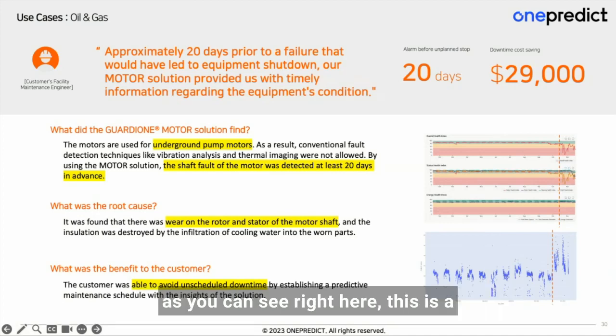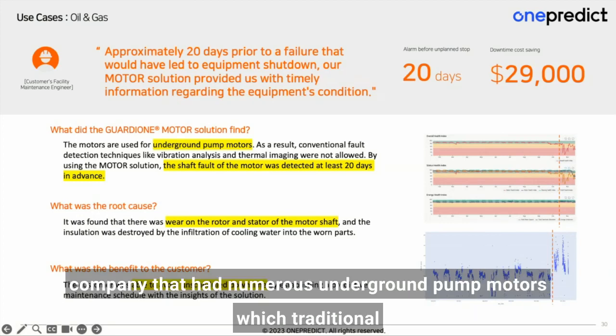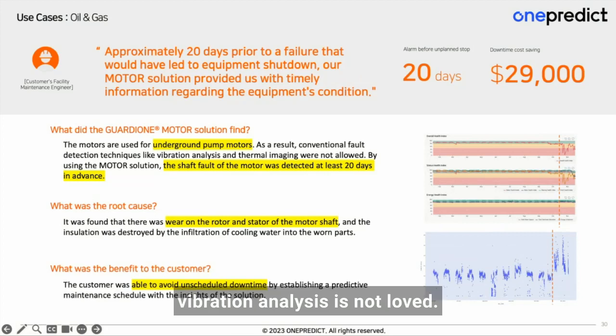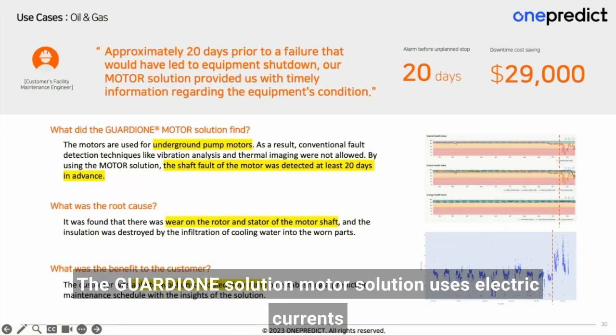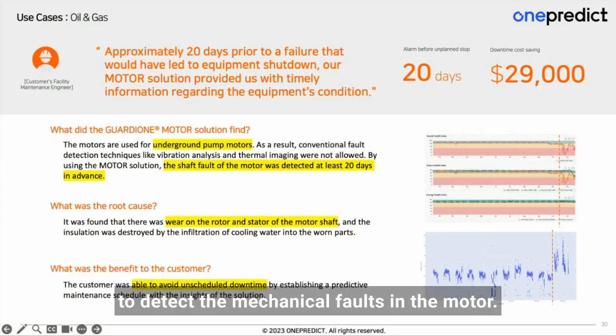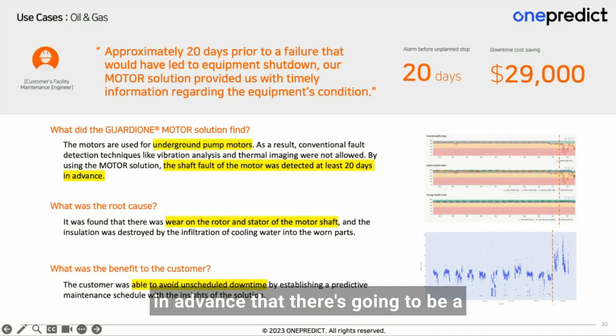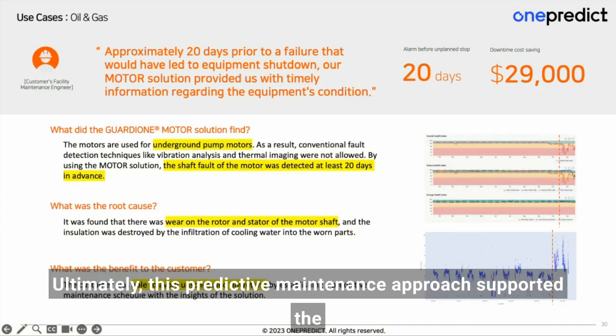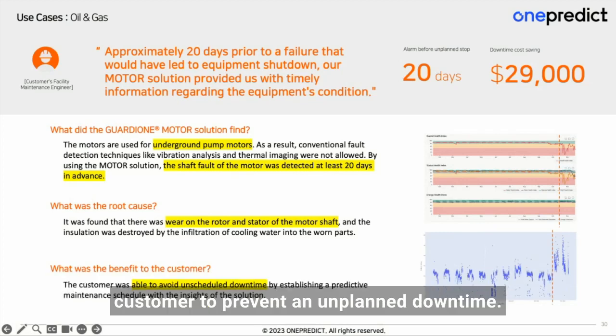In the first use case, this is a company that had numerous underground pump motors, where traditional vibration analysis is not allowed. The GuardiOne motor solution uses electric currents to detect mechanical faults in the motor. We were able to predict 20 days in advance that there's going to be a failure, thus saving around 29,000 USD. The wear on the rotor and the stator is the root cause of the fault.